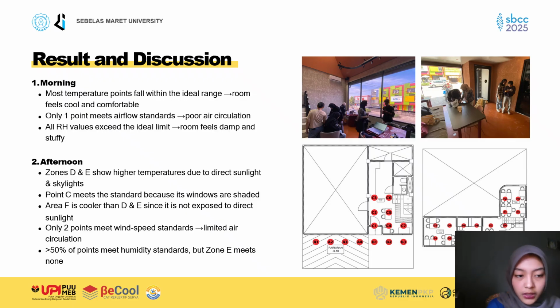In the afternoon, zones D and E show higher temperatures due to direct sunlight and the skylight. Point C meets the standard because the windows are shaded.